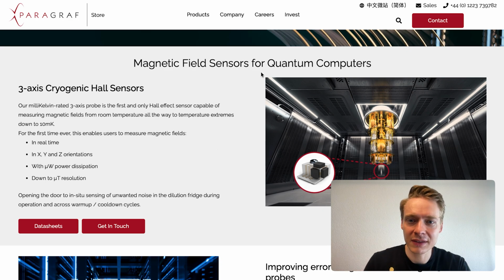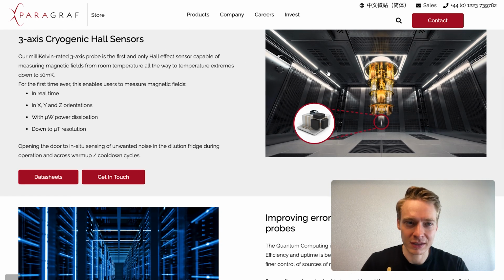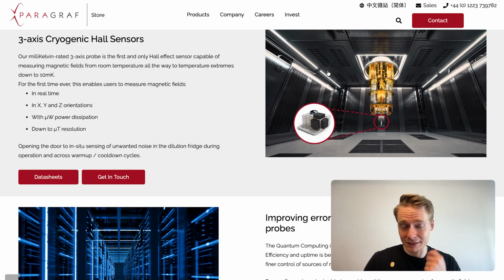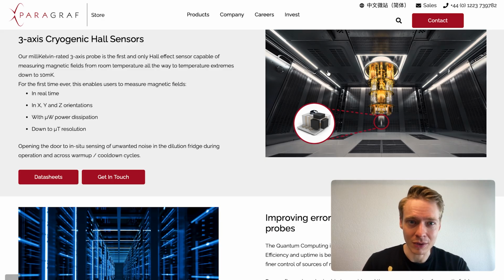So magnetic field sensors for quantum computers, 3-axis cryogenic Hall sensors. So our millikelvin rated 3-axis probe is the first and only Hall effect sensor capable of measuring magnetic fields from room temperature all the way to temperature extremes down to 10 millikelvin. For the first time ever, this enables users to measure magnetic fields in real time in X, Y, Z orientation with microwatt power dissipation and down to the microtesla resolution, opening the door to in situ sensing of unwanted noise in the dilution fridge during operation and across warm and cool down cycles.